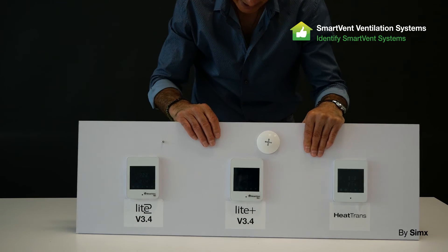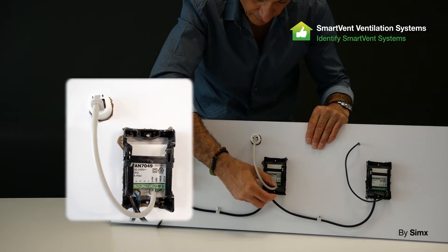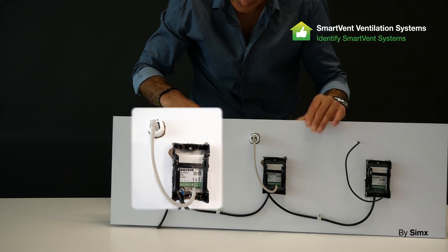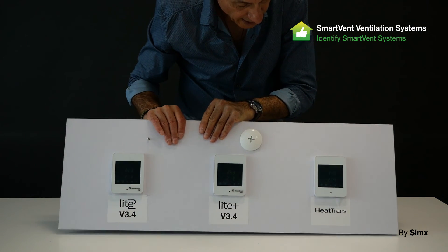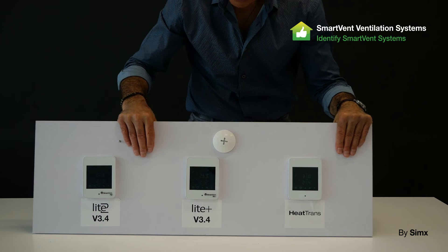We then developed the Lite+. The Lite+ uses the thermostat and humidity sensor combined, wired into the back of the wall controller by the same terminals. To connect it, you cut the RJ45 cable and use the specific wires that go to the connections at the back.